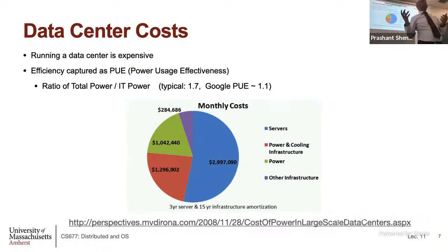Okay, now, because that increases your electricity bill, there's been a lot of research on how to reduce the power usage effectiveness of the data center, or just how to make the data center more energy efficient. The ideal value is now coming down, and the most efficient data centers that you see today have PUE values of 1.1 or lower. So they are maybe 1.07, 1.1. What that means is they made the cooling extremely efficient.